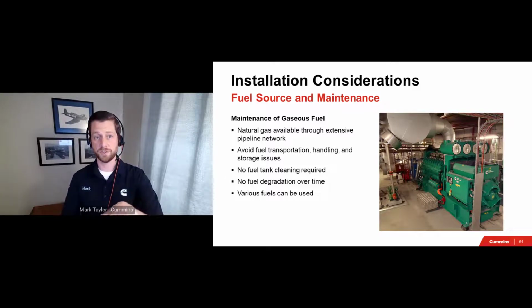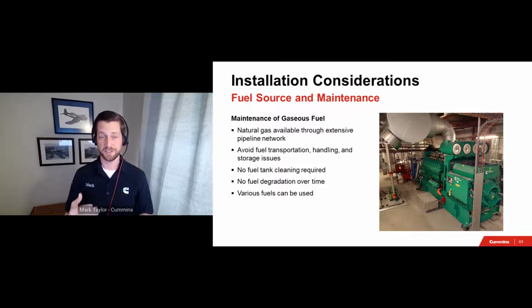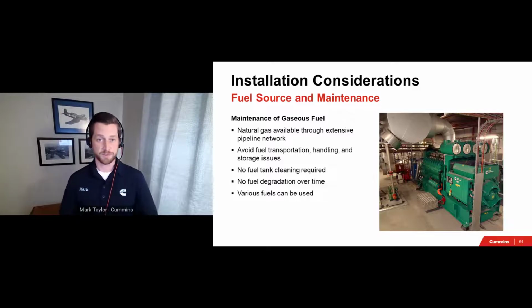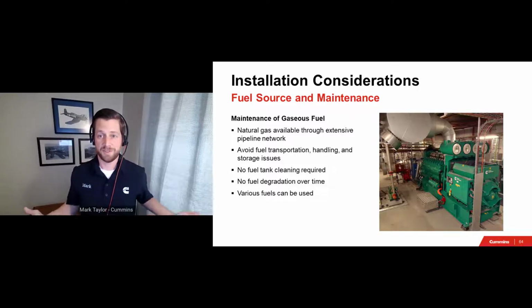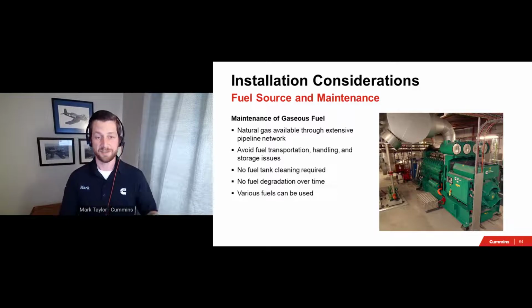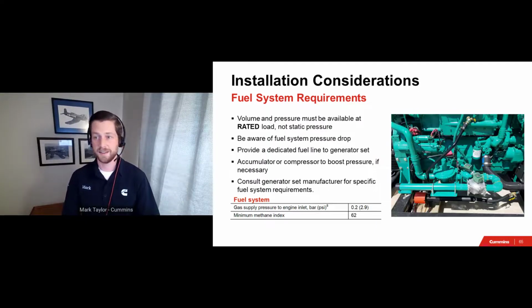Compared to on-site storage requirements of diesel, gaseous fueled generator sets can potentially be much easier. As we mentioned earlier, if an installation can solely rely on the gas utility as the sole source of supply, then it doesn't have to be concerned at all with the items that we cited. If on-site storage of gaseous fuel is needed, for example, propane, that fuel does not go bad, and it is sealed from the environment under pressure. Its shelf life is basically limited to the life of the tank. That all said, this is not to say that gaseous fueled generator sets are without nuance.